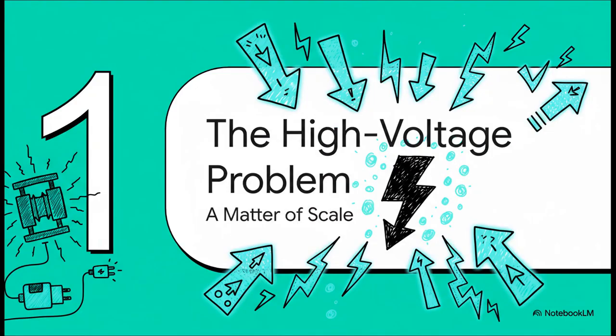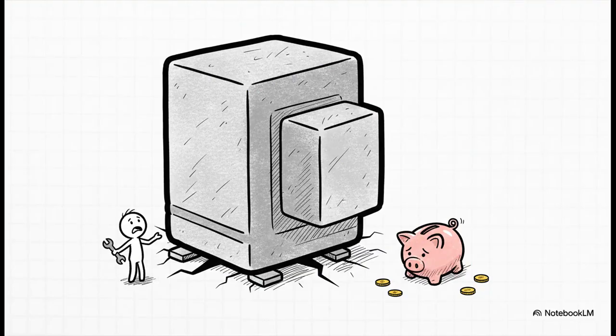Let's find out. For a long time, the standard tool for stepping down voltage was the potential transformer. It works on the principle of magnetic induction, kind of like your phone charger, but on a much bigger scale. But when you try to apply that same idea to grid-level power, you run into a huge problem. Once you get above about 100 kilovolts, a normal magnetic transformer would have to be absolutely gigantic, unbelievably heavy, filled with vast quantities of insulating oil, and just crazy expensive. It's simply not a practical solution.